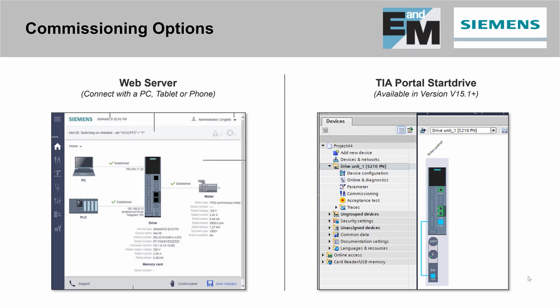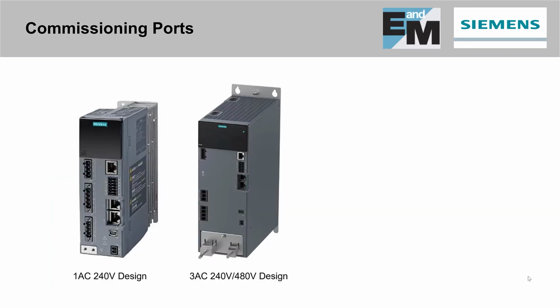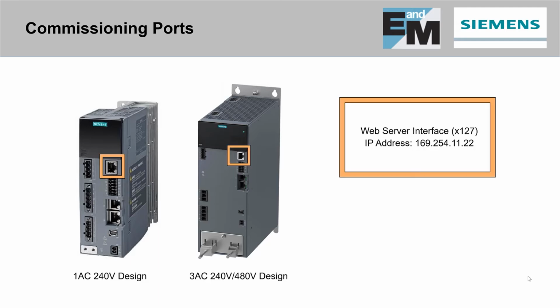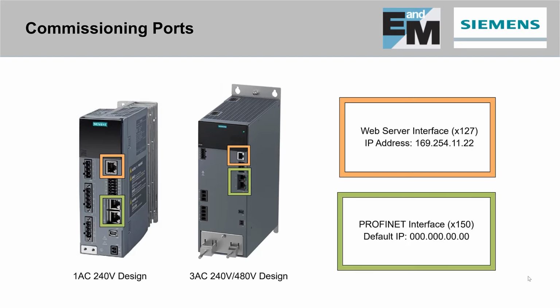Not only does this option allow you to commission your S210, but you can also set up your PLC and HMI and have all of these 3 components included in just a single project in TIA Portal. Let's review the commissioning steps through both options. First, we'll connect to the web server port and use a PC to access the web server via the IP address.